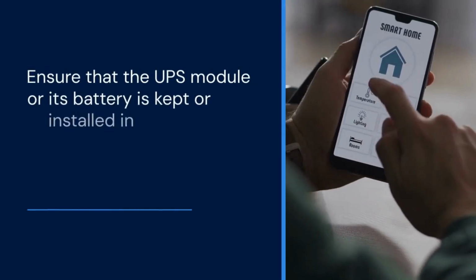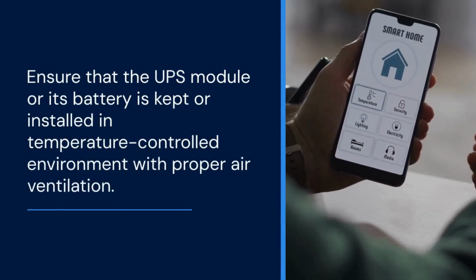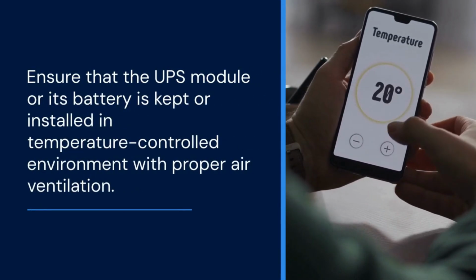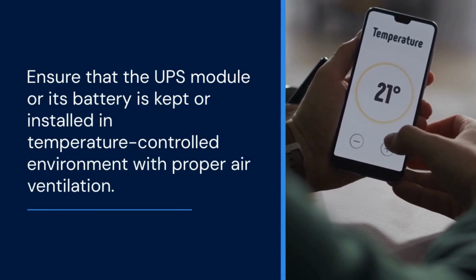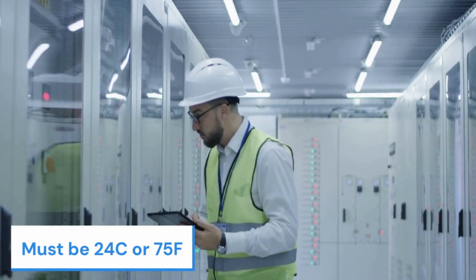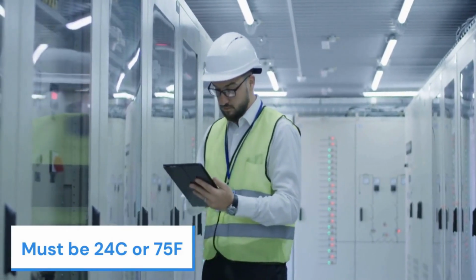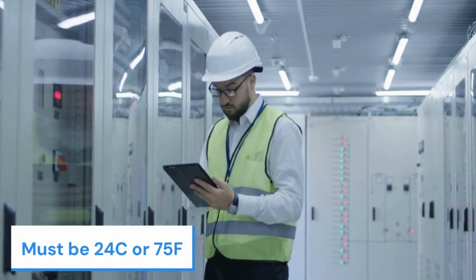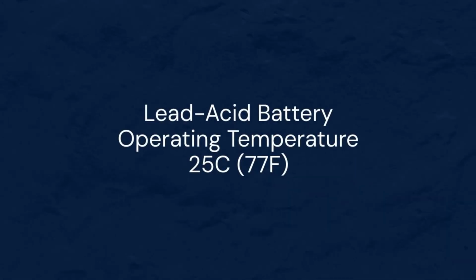A. Ensure that the UPS module or its battery is kept or installed in a temperature-controlled environment with proper air ventilation. The optimal ambient temperature should not exceed 24 degrees Celsius or 75 degrees Fahrenheit. B. The optimal operating temperature for a lead-acid type battery is 25 degrees Celsius or 77 degrees Fahrenheit. Higher ambient temperatures can reduce battery life.